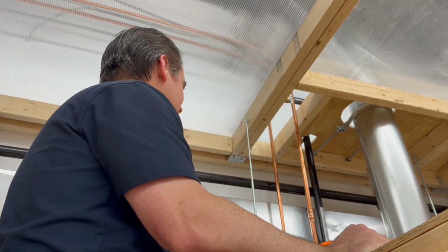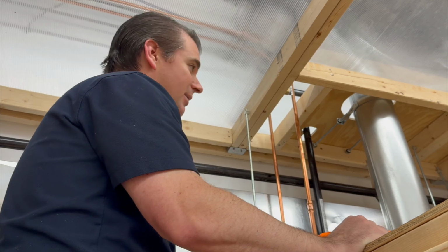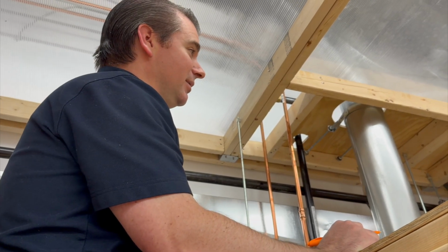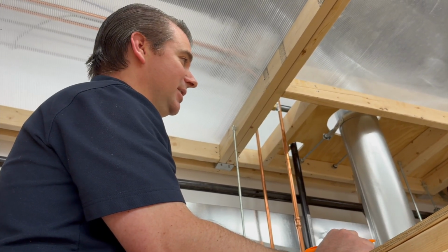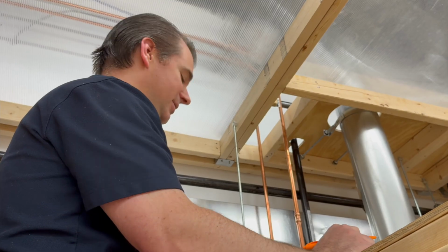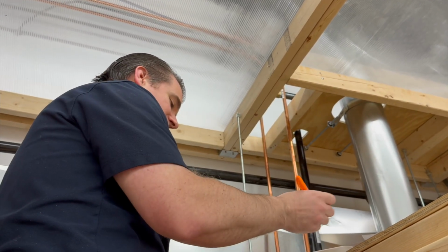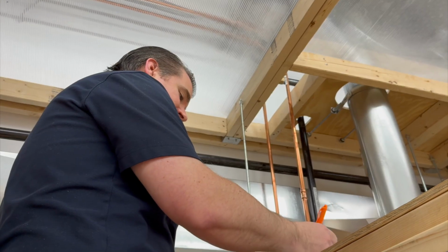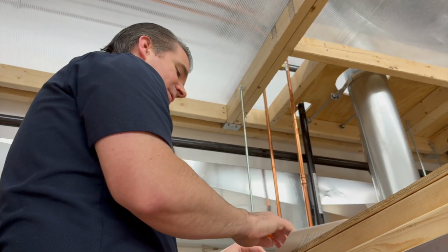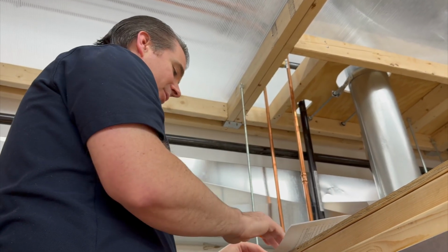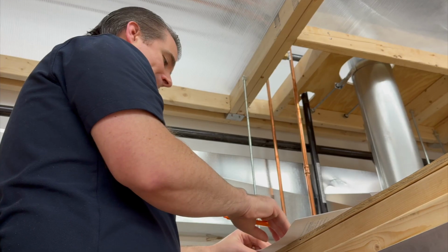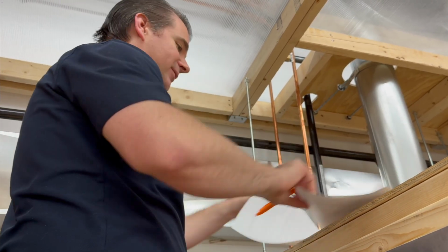It doesn't look like any duct sealing has been completed on it. Looks like one of the flexible ducts at the far side is maybe slightly kinked. It makes a sharp bend. This one here is missing insulation, so I'd say the ducts are in poor condition. Again, if there's no insulation, the R value would be 0. That's all that's needed for that section.